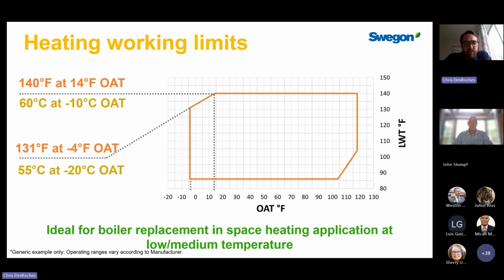On the topic of water temperature, just a quick refresher too, these heat pump units have liquid injected compressors. So this means we can do a much higher supply temperature and better supply temperature at low ambient conditions. So today's generation of air-to-water heat pumps, thanks to liquid injected compressors, are able to generate typically 140°F water down to 14°F, and can operate down to -4°F while still producing 130 degree water.